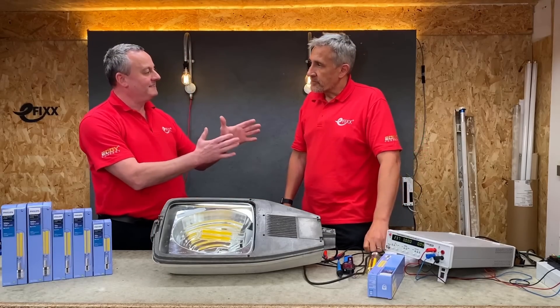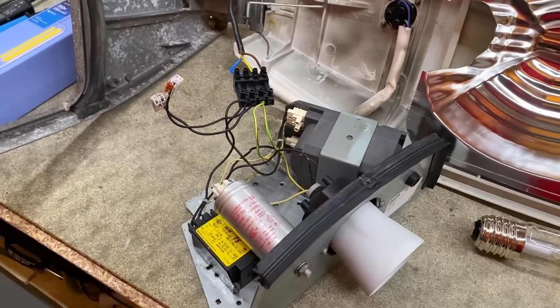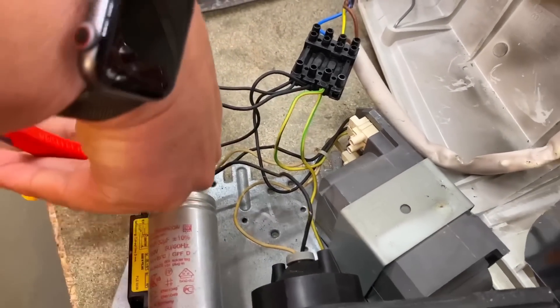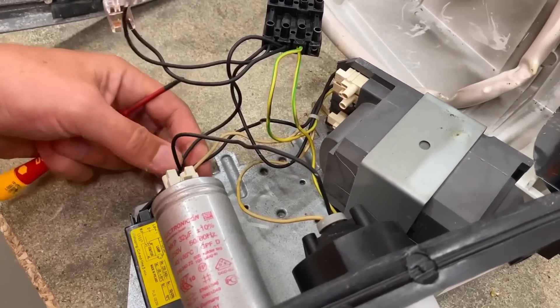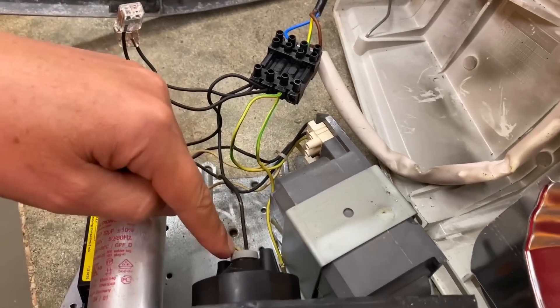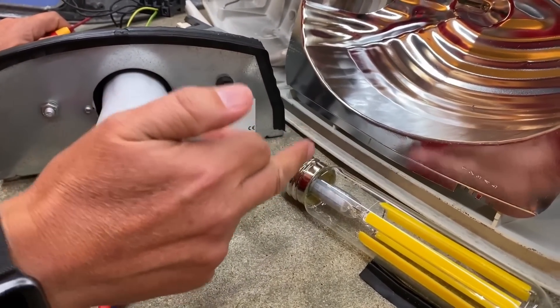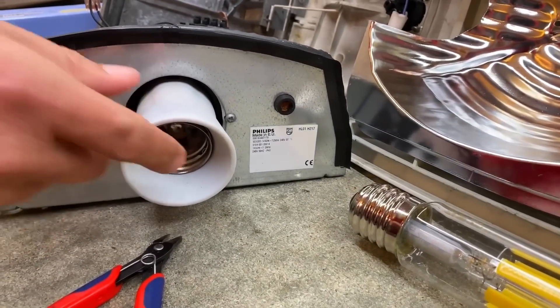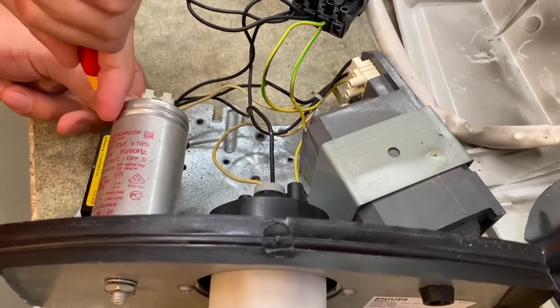If I've gone to the trouble of taking out the capacitor, why not just take everything out and go direct to mains? So we're going to look at how we remove all of the control gear and convert the lamp to direct mains. First, I'm just going to snip off these cable ties. It looks more complicated than it is, but it is actually quite a simple process. So we've got an igniter, we've just removed the capacitor, and we've got two wires coming from our lamp cap. It is an Edison screw lamp cap, so the last thing we want is the line terminal on the large metal contact area you can easily put your finger on. Once we've identified and stripped them back — keeping them as long as possible — we're identifying the neutral and line to get the Edison screw polarity correct.